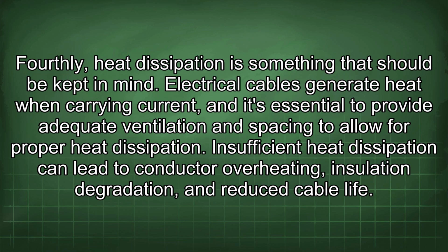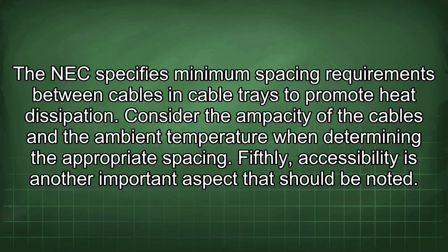Fourthly, heat dissipation is something that should be kept in mind. Electrical cables generate heat when carrying current, and it's essential to provide adequate ventilation and spacing to allow for proper heat dissipation. Insufficient heat dissipation can lead to conductor overheating, insulation degradation, and reduced cable life. The NEC specifies minimum spacing requirements between cables in cable trays to promote heat dissipation. Consider the ampacity of the cables and the ambient temperature when determining the appropriate spacing.